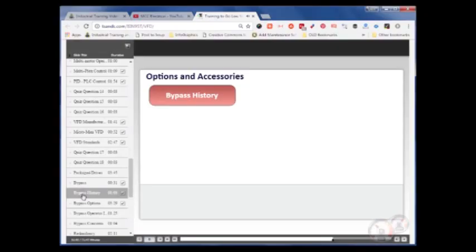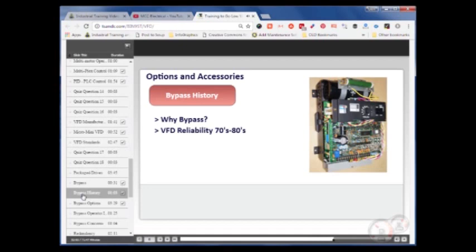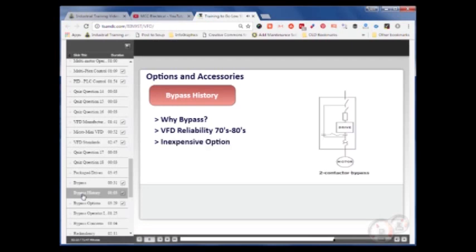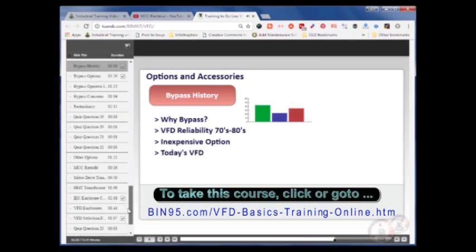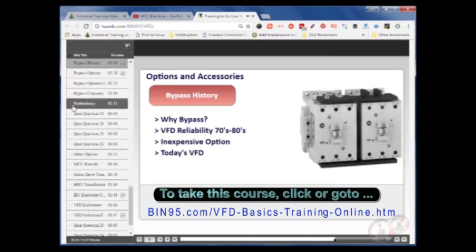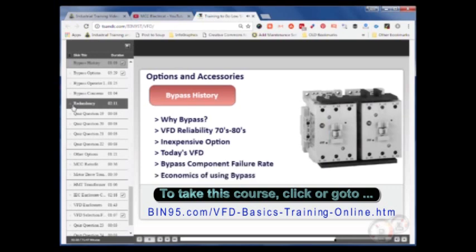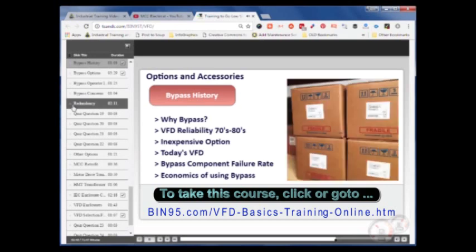Now why do engineers specify bypass on drives? The primary reason is to keep machines, especially those of critical nature, running. It is an outcome from the 1970s when VFDs were in the early stages of development. There were many failures with the circuit boards and SCRs. Customers were anxious to obtain energy savings, but the high failure rates caused manufacturers to offer bypass packages as a backup. Bypass was considered a low cost method to keep the motor running in case with a VFD going down. Today's VFD failure rates are approximately 0.25%. In many cases, the bypass components fail at a higher rate than the VFDs. Therefore, the cost appropriated for bypass components in some cases are better suited channeling toward a spare drive. This is especially important if the spare can serve as a backup for several drives inside a plant.